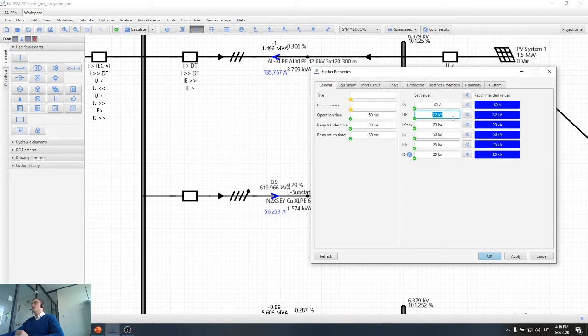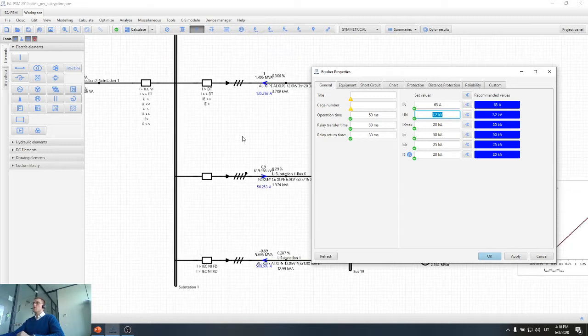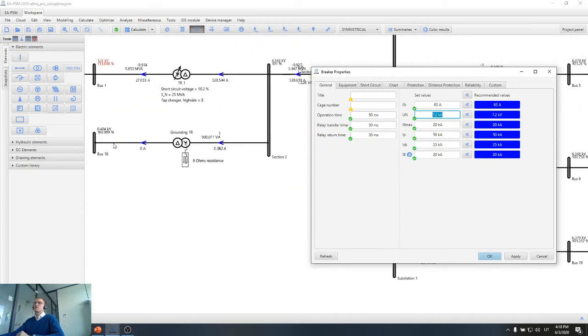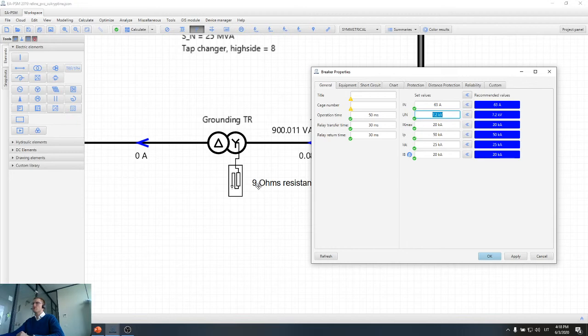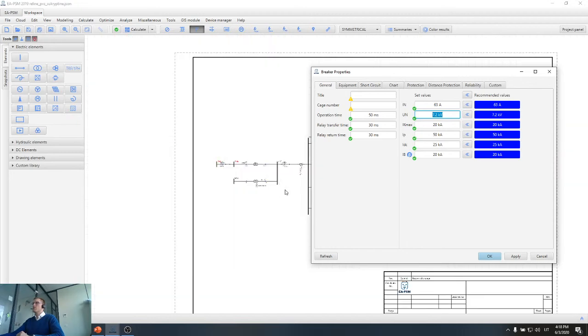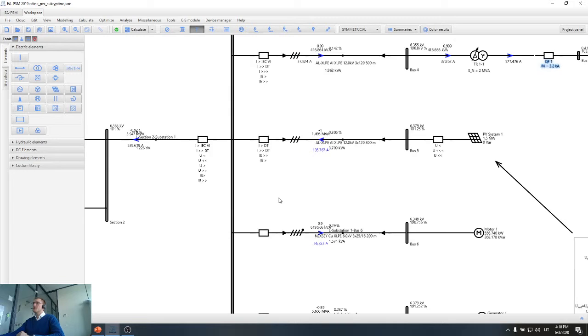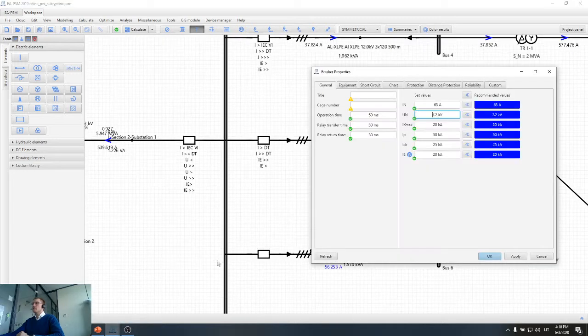This is because during single phase short circuit, voltage will increase significantly in this kind of network due to voltage drop in the grounding resistor. So here I have 9 ohms grounding resistor, so therefore voltage will increase, and our breakers should be capable to withstand this voltage increase, and therefore software already recommends bigger voltage nominal than network voltage nominal.